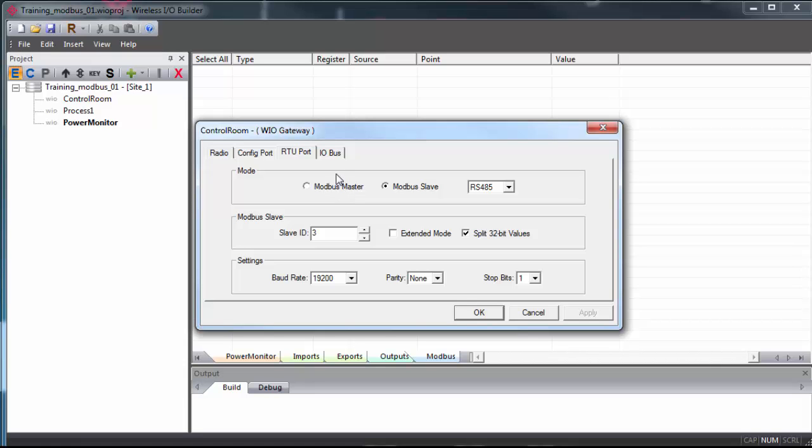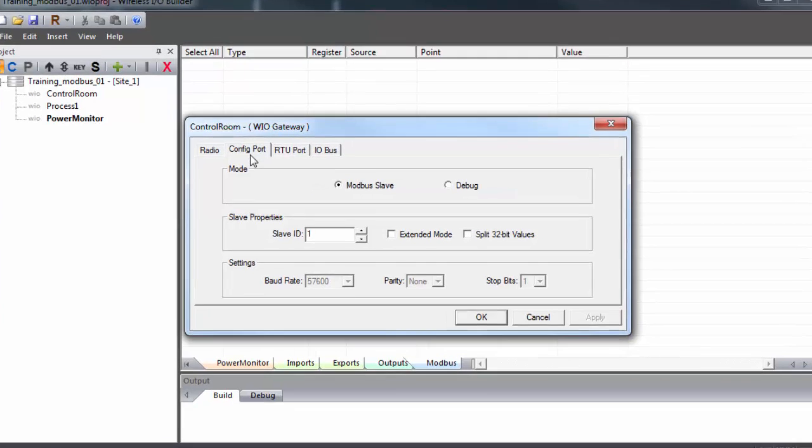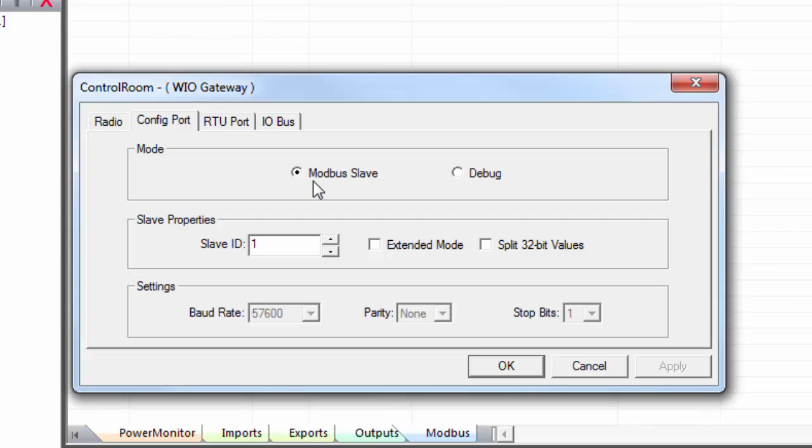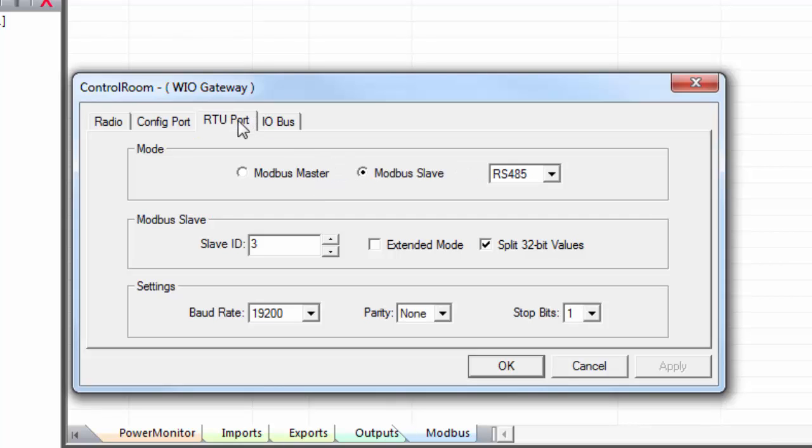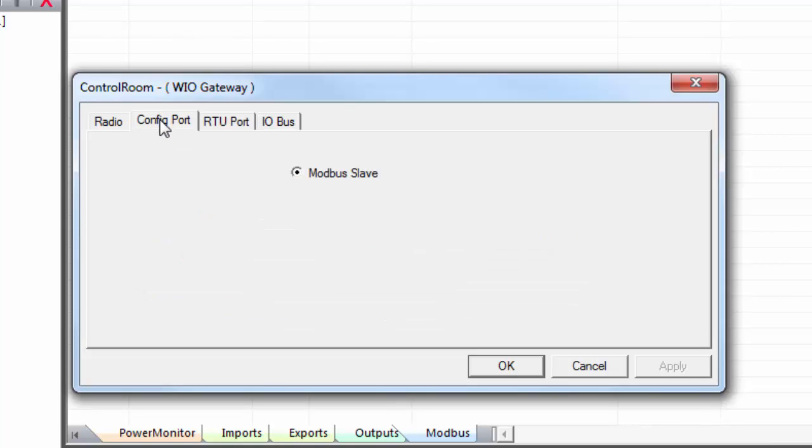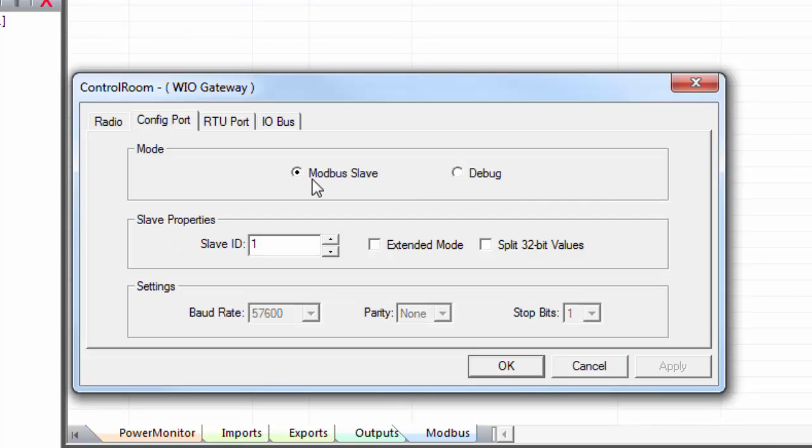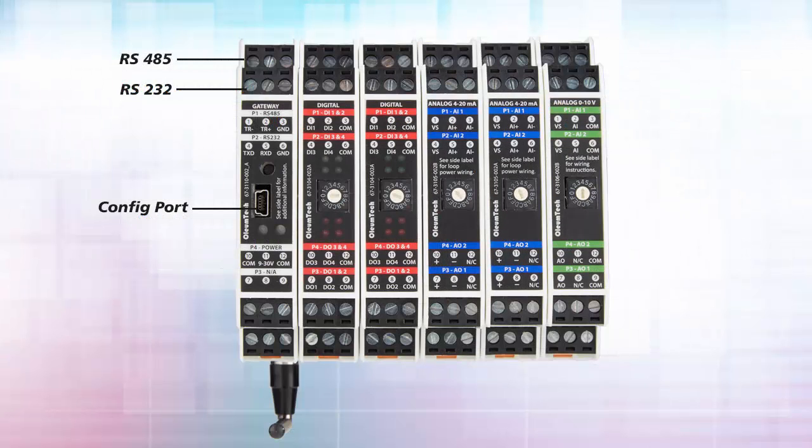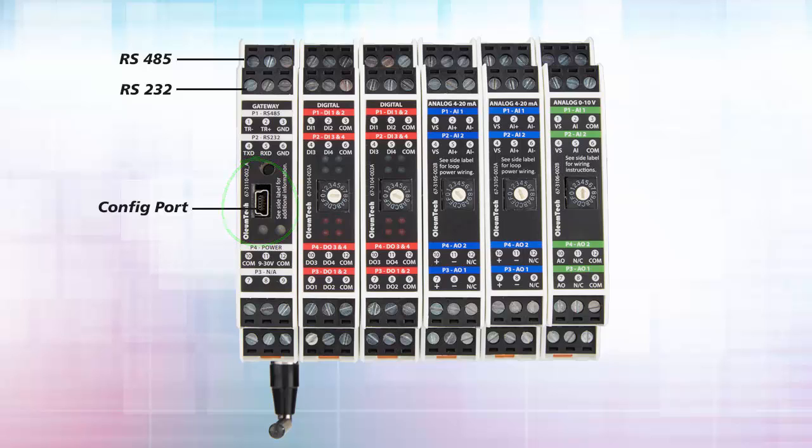Now we set the config port to Modbus slave, and you can see under RTU port that we have the option to set it as a Modbus master or slave here. So the Modbus slave mode under the config port creates a master-slave dynamic between your PC and the gateway, allowing your PC to pull Modbus registers through the config port on the front of the gateway. It actually has no effect on the RTU port settings, which apply to the physical RS-232 and RS-485 pinouts on top of the gateway.